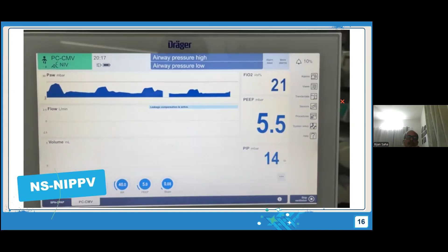What do you mean by synchronization? Next slide, please. Next slide. So synchronized means once the baby is taking inspiration, the ventilator will be in the inspiration phase. When the baby is in the expiration phase, the machine will also be in the expiration phase. But what will happen if the baby's breaths are not synchronized?